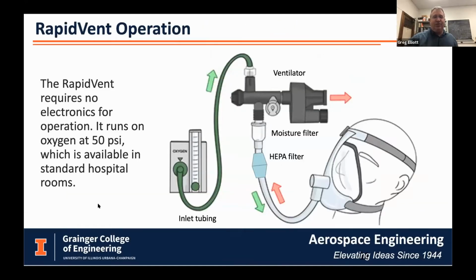And just to show you the layout of this, if you've ever been in a hospital, they have an oxygen supply there. And so we used that oxygen as the supply of not only the oxygen to the patient, but it also was the driver of the ventilator. That's the advantage of this: there are no electrical connections needed. The oxygen that comes out of a hospital, we went over and measured it and verified it. It is provided at 50 psi and has a flow meter there that can be adjusted.